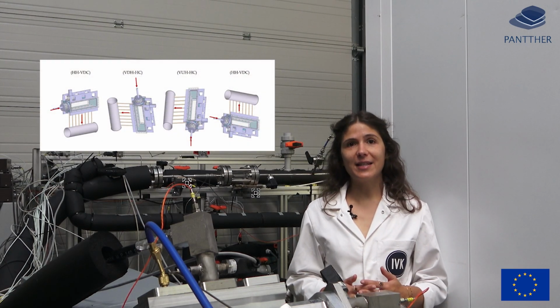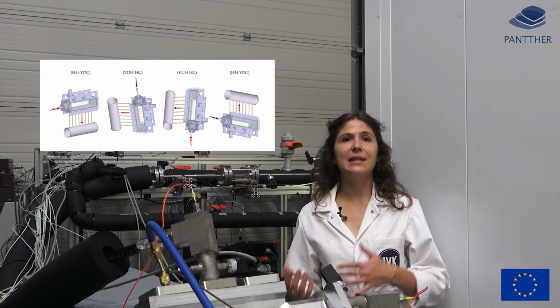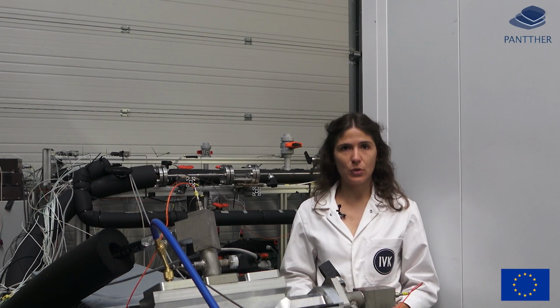So the second step of the PANTTHER project was to test this instrumentation on a simplified evaporator, so basically a header connected to channels. So the instrumentation was mounted on the channel to be able to measure the two-phase flow mass flow rate inside each channel, and then we were able to assess the two-phase flow distribution inside these channels. Several combinations of parameters were tested, such as we changed the inlet diameter, the inlet position, we put also a splashing grid, an accessory at the inlet to disperse the liquid phase inside the whole header. So we tested several combinations of parameters, and we were able to retrieve their impact on the distribution.